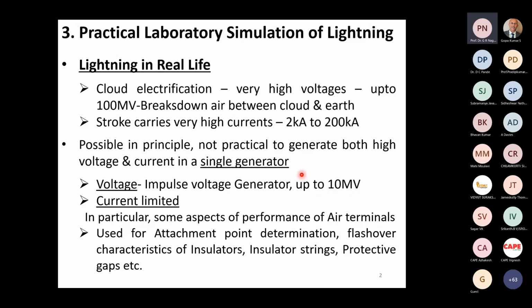Therefore, what is done is the voltage is generated separately in what we call an impulse voltage generator. Up to 10 megavolt impulse generators are available in the world. These are what are called nominal voltages, and typically the efficiency is between 80% to 90%. So the maximum output voltage can range right up to about 9 megavolts. But in these voltage generators, the current is limited, typically maybe 5 kiloamperes to possibly up to 20 kiloamperes.